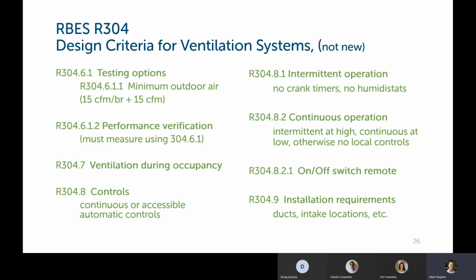Here we go again. Still, the stuff's not new for design criteria and ventilation systems. There's testing options. There's performance verification. For testing options, you must measure based on 304.6.1. They give you what they're looking for, how we measure them. We need to ventilate only during occupancy. There's criteria for controls. There's criteria for intermittent operation and continuous operation. There's criteria for where the on-off switch goes. There's criteria for installation requirements on the ducts, which concerns intake locations, how the ducting should be done, etc. So be familiar with all of these aspects of the code. RBES 304 spells it all out for you, how to do ventilation systems.